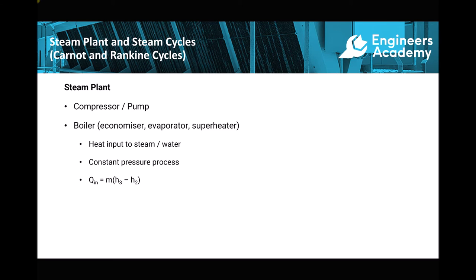The next device in the system is the boiler. We can have a boiler that heats steam, or one broken down into various components: an economiser that heats water, an evaporator that evaporates that water and converts it into steam, and a superheater that superheats the steam after it's reached its dry saturation point. In both instances the boiler is used to input heat to the steam or water at constant pressure. The heat input is calculated as the mass of water or steam passing through the boiler multiplied by the change in enthalpy — the enthalpy at the exit minus the enthalpy at the entrance.